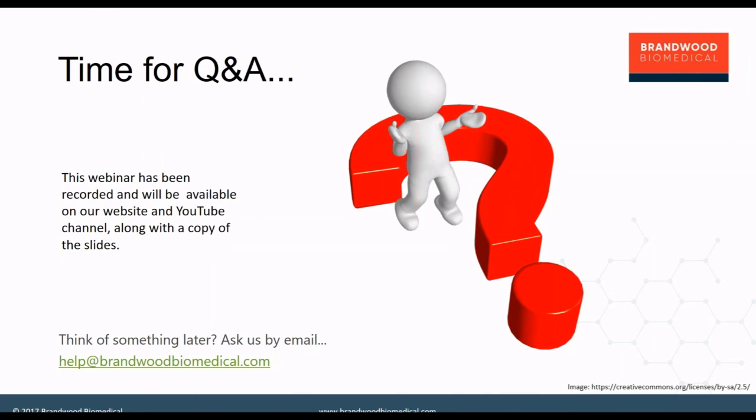And obviously, the other aspect to that is that you will need to make sure that your clinical evidence contains information that is representative of the local clinical practice. So make sure that if there are different clinical practices in those various countries, this is verified and incorporated in the assessment or in the evaluation report, and that you currently represent the body of knowledge for the target jurisdiction.